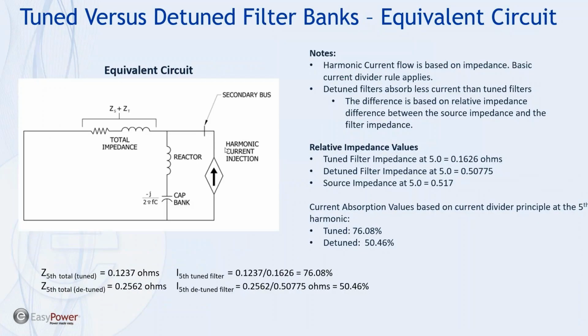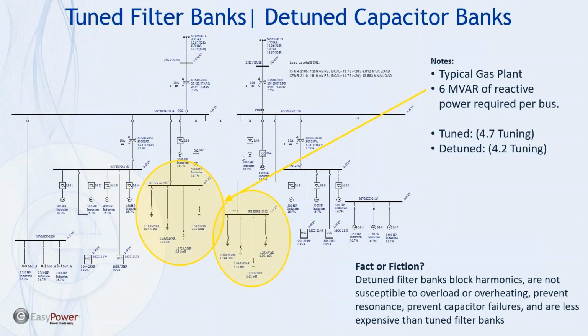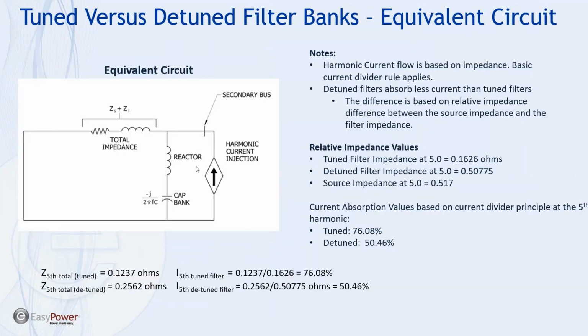So we go back to this slide first, and we note that if we're sitting at this bus, harmonic current injected from these drives here have a choice. Okay, they can flow back towards the source, or they can flow back into the harmonic filter. We can represent this system here with just basically two impedance values, a source impedance here and a filter impedance here. So back to this slide, we have our harmonic filter here. It's an equivalent impedance of the filter, and we have our impedance of the source here.